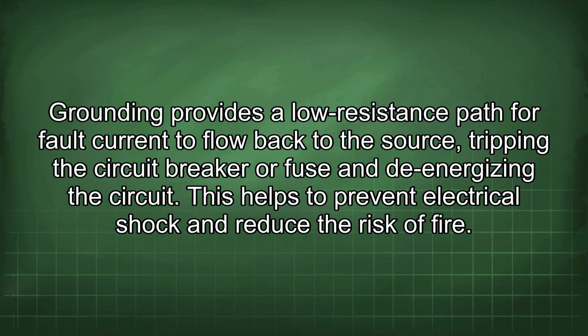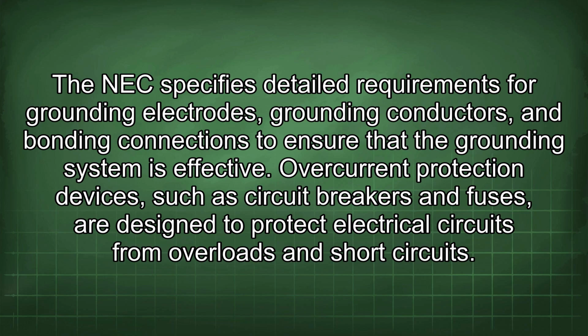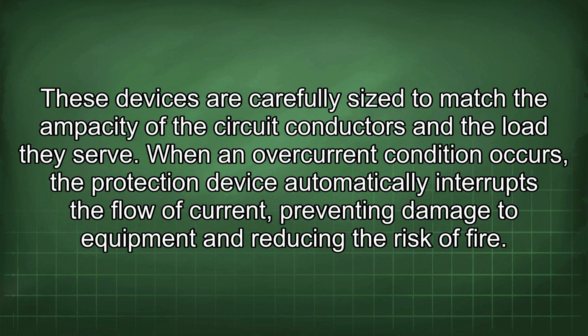This helps to prevent electrical shock and reduce the risk of fire. The NEC specifies detailed requirements for grounding electrodes, grounding conductors, and bonding connections to ensure that the grounding system is effective. Overcurrent protection devices, such as circuit breakers and fuses, are designed to protect electrical circuits from overloads and short circuits. These devices are carefully sized to match the ampacity of the circuit conductors and the load they serve.